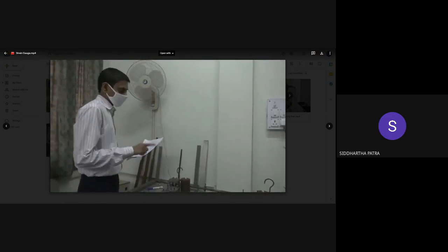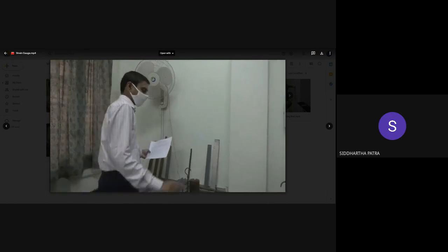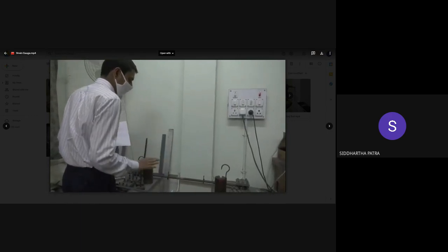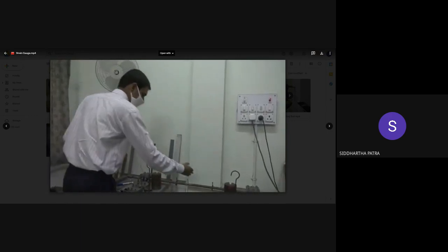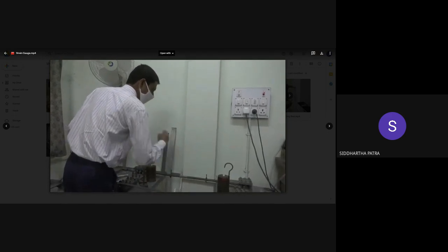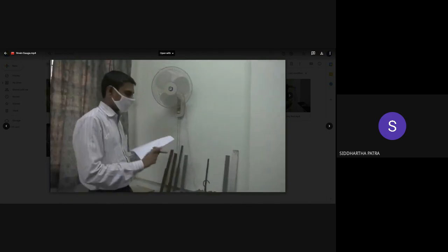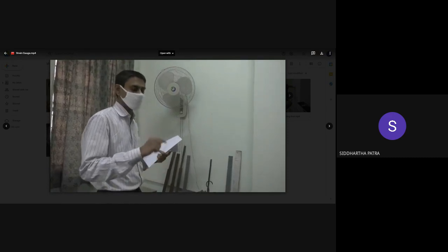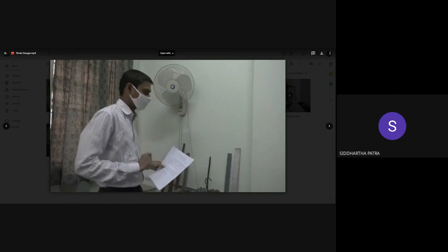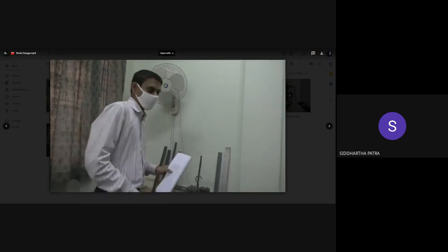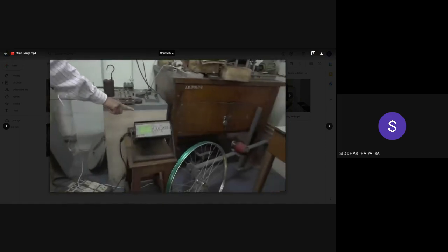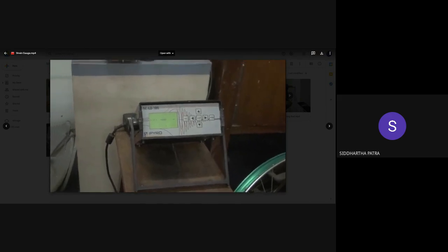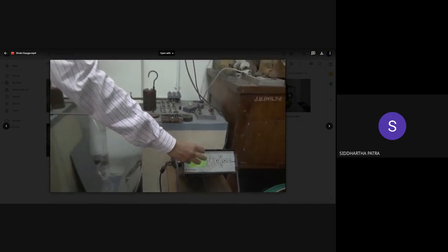Now, if we use this half bridge case, the arrangement with the help of this Wheatstone bridge circuit will be made in such a way that the positive strain due to tension and the negative strain due to compression will both be added, value-wise, making the sensitivity twice compared to the quarter bridge case. The strain indicator system is used here in such a way that whatever strain is induced can be read directly. There will be no conversion.